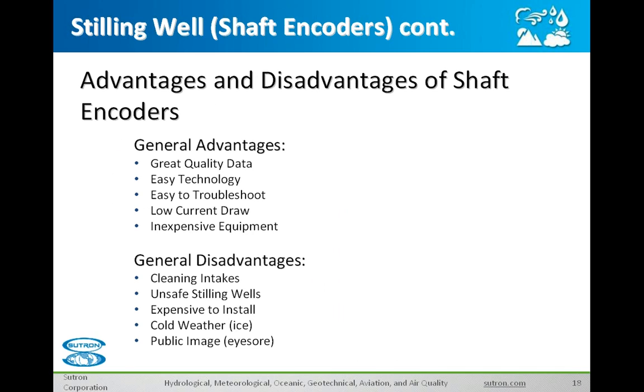Some general advantages and disadvantages of using a shaft encoder: The advantages are you get great data — they're very accurate, especially if your float never gets hung up in the well. It's easy, simple technology, which makes it easy to troubleshoot. Everything works off the shaft turning, making it really nice to diagnose. The equipment itself draws very little current, so you don't have to worry too much about power with the sensor itself, and the equipment can be very inexpensive.